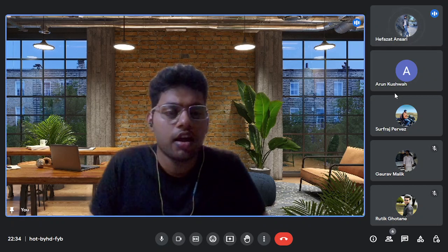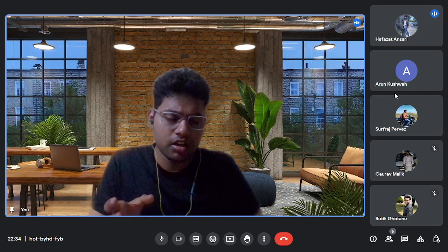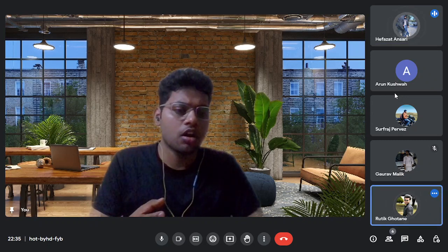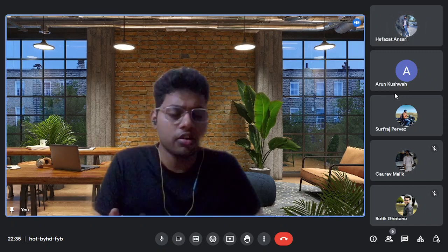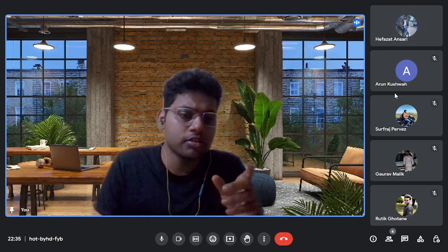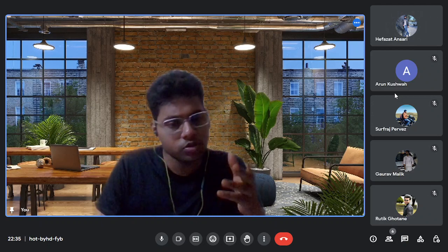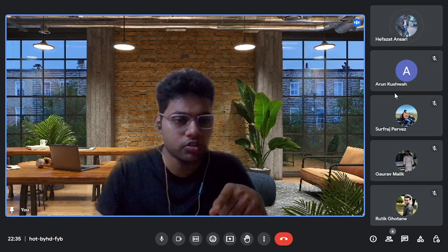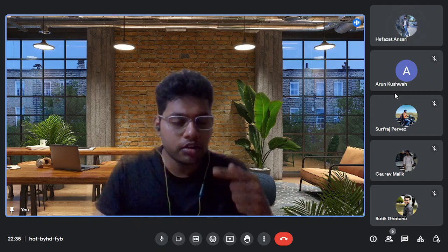I have made this answer short and concise. Since air is compressible and has a density 1000 times lower than water, what will happen? And density, you missed density. So yeah, since the air density is 1000 times lower than the density of water, the centrifugal force will decrease by 1000 times by the formula m v square by r. M is rho into v, so rho will decrease by 1000 times, so the force will also decrease by 1000 times. So it will not be able to create enough suction pressure, enough negative pressure at the eye of the impeller, and so the fluid will not be sucked and the impeller will run dry.